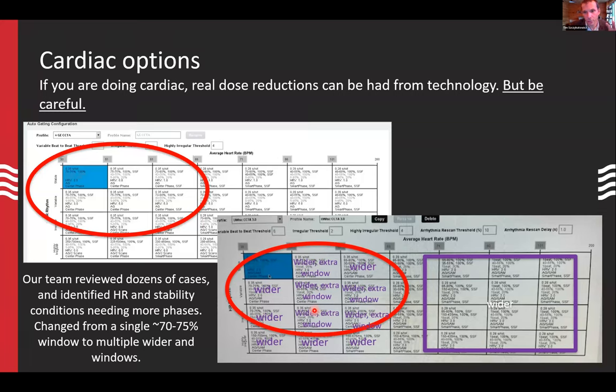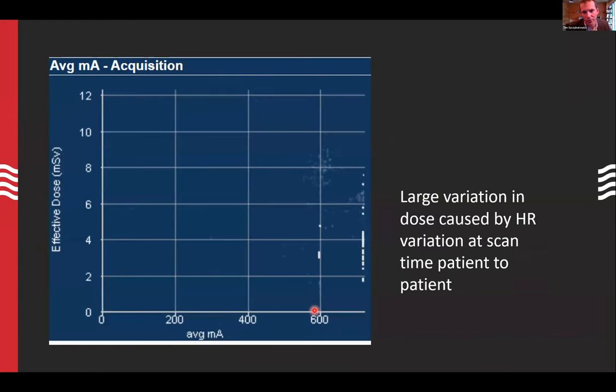With a smart algorithm like this, technologists don't have to make scan time decisions between one protocol versus another. But we do have to know this, because when we put our QA or QC hat on and look back at historic dose data, a system like this will have a lot of variation in doses that have nothing to do with patient size, but are actually tied to the patient's heart rate. That can be new to some folks who aren't used to this. These scanners control how much dose they deliver based on heart rate and heart rate variability, so we've got to understand this.